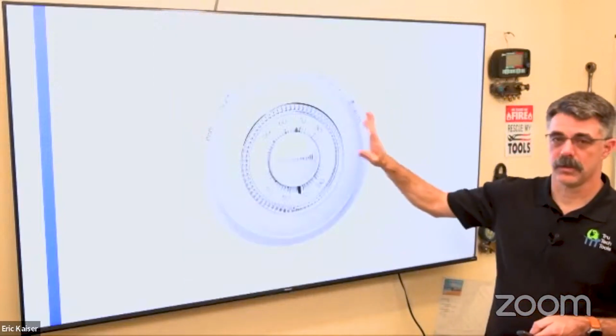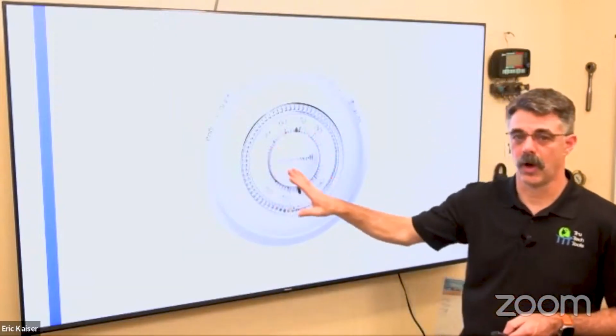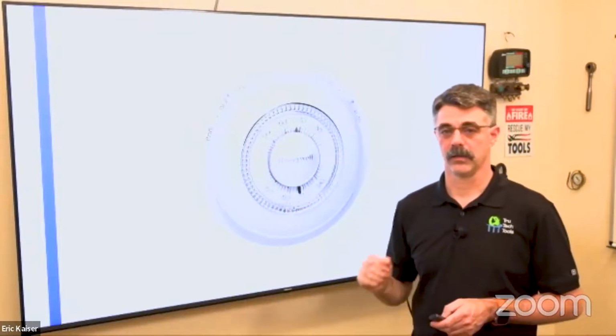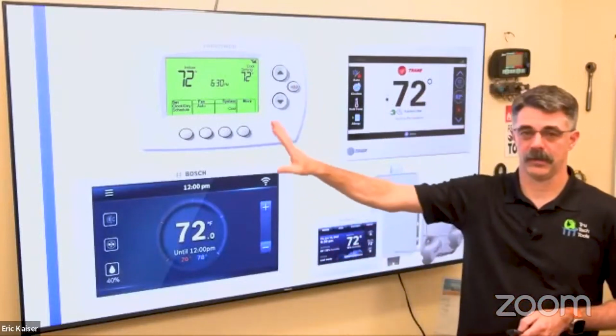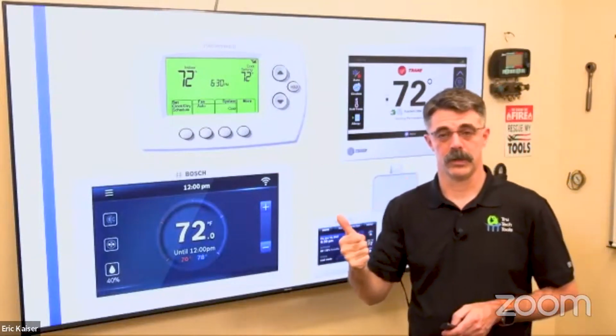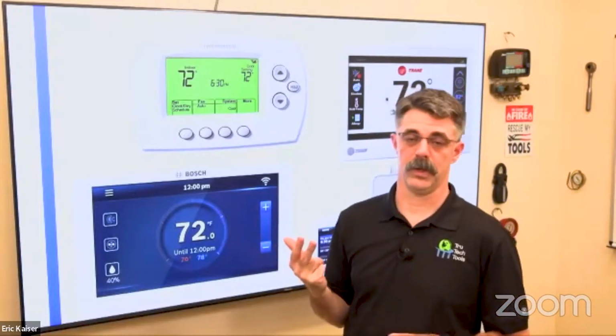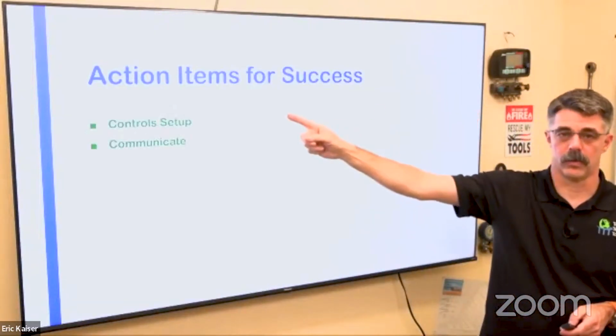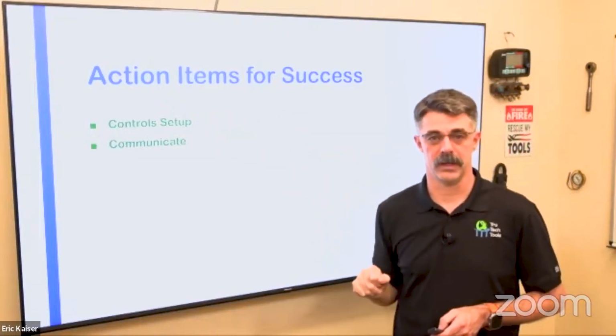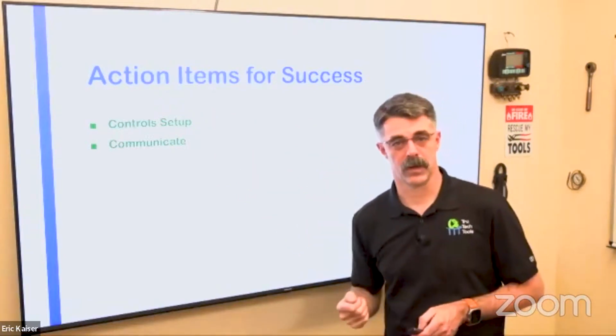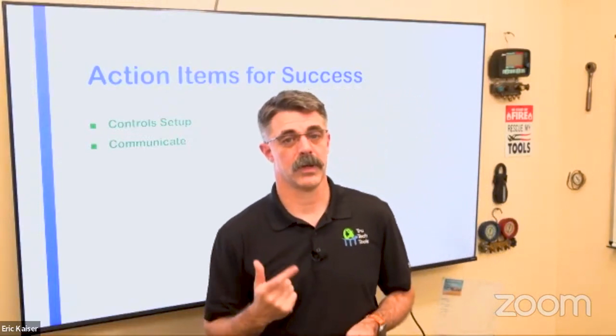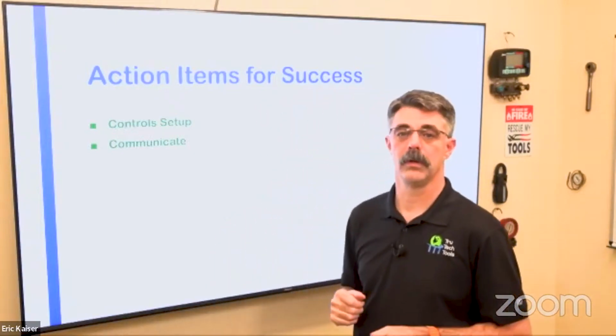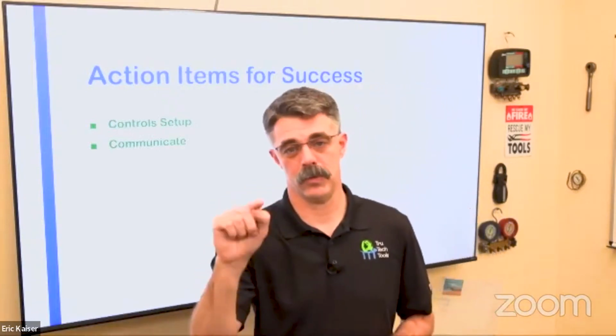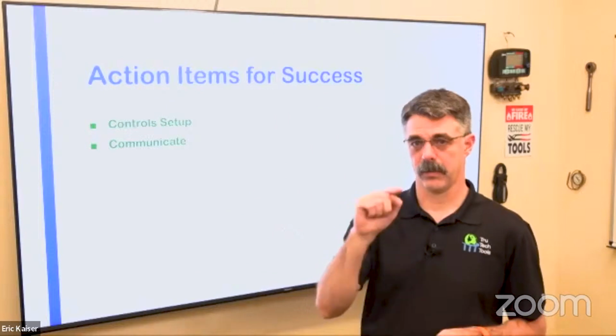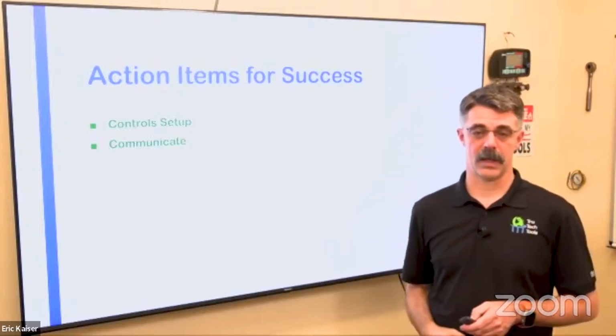Right? Make sure you're selecting a good control system. Our control systems are not simple on-off anymore with this, right? They're going to have a couple extra settings in them. So make sure you're selecting a control system that does what you want it to, has the control logic, and works with the equipment that you're putting in. Okay? Now, make sure your controls are set up to operate the way that you designed it. And then communicate to the customer. Communicate how the system is going to operate and how to operate the controls. Walk them through it. As you're walking them through it, have them do the actual operations, not you. Just tell them where to press and what that's doing. Make sure they get it.